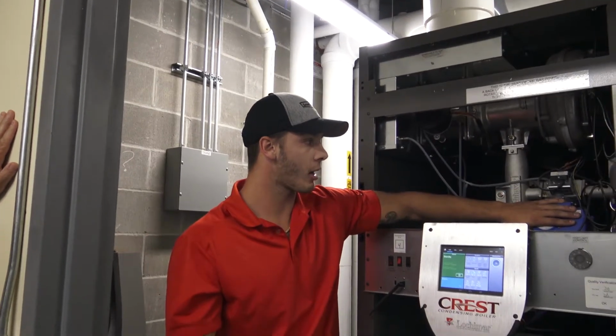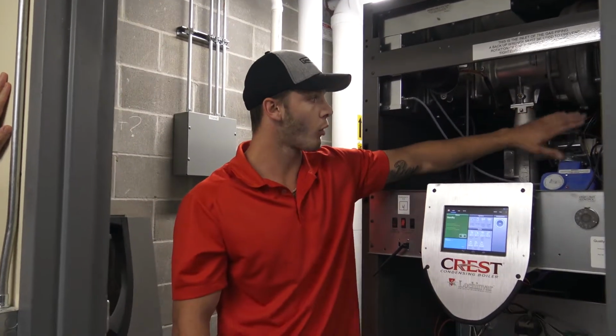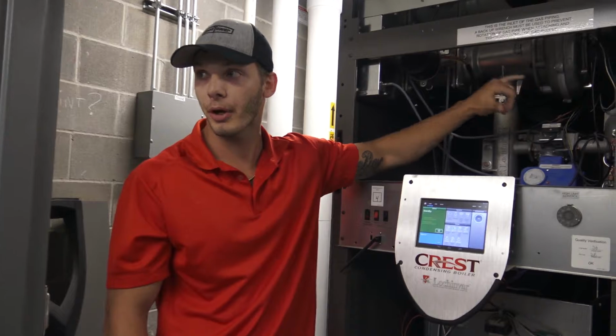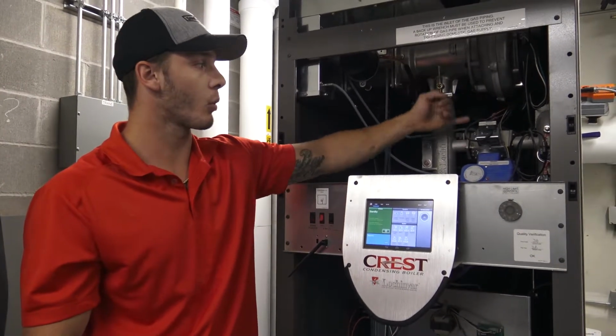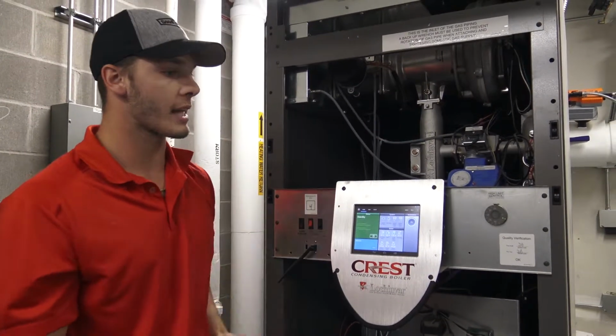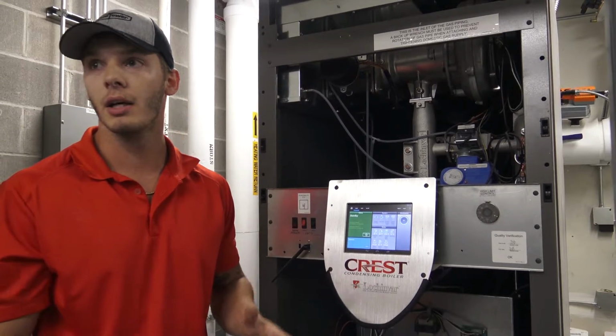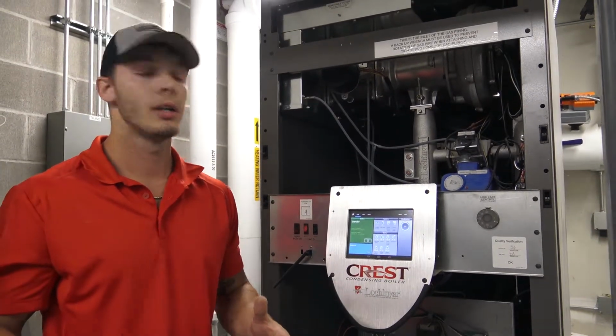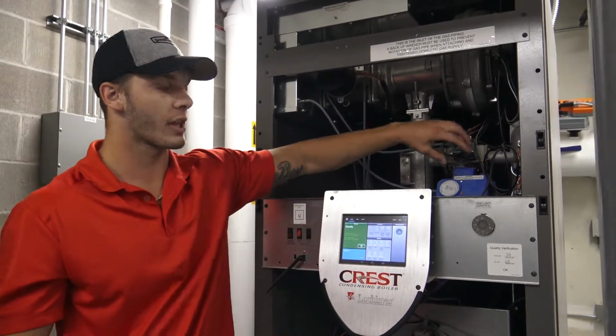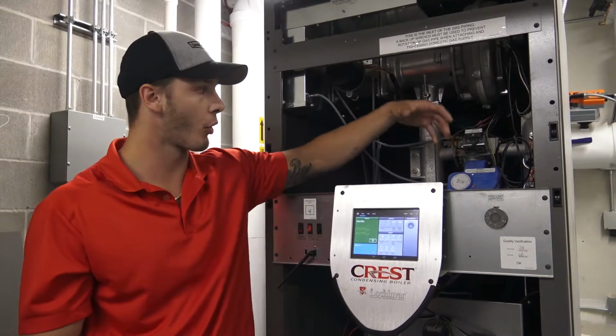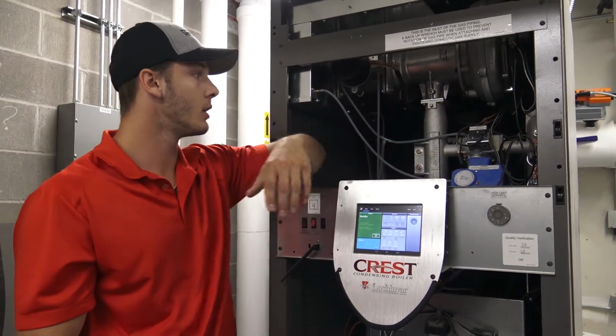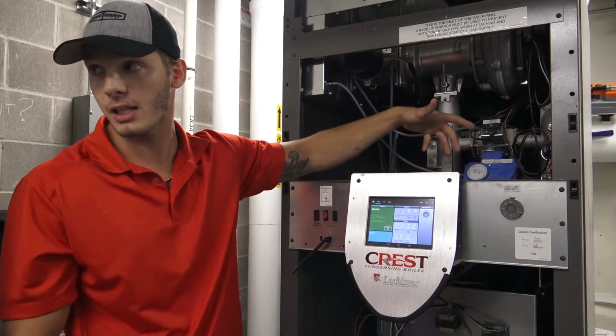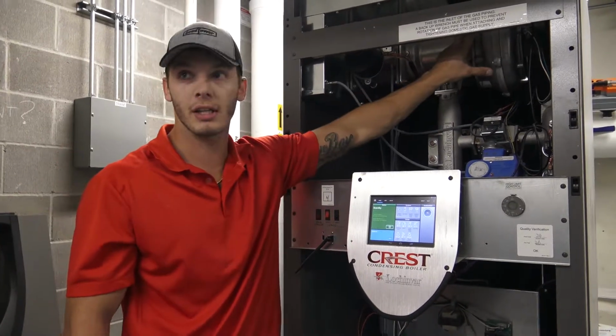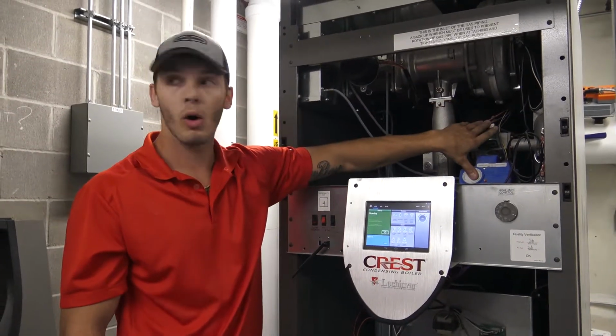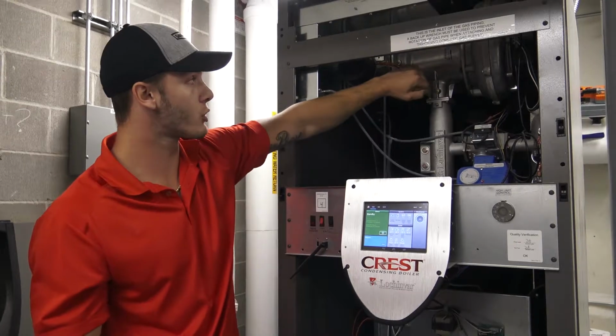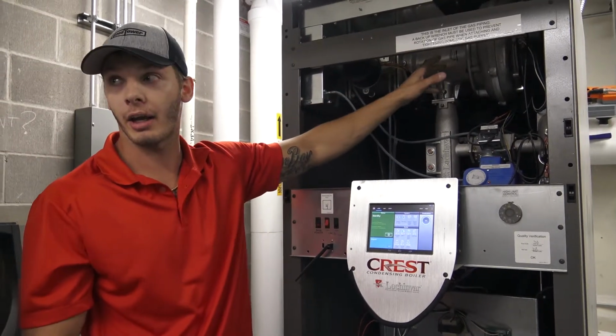This is your blower. It is going to be pulling outside air. High gas pressure valve, so high fire valve, low fire valve. They will not operate at the same time. It's going to be one or the other. So once it hits past 25%, it's going to go into high fire, and it's going to switch over to this Honeywell gas valve. Both modulating gas valves, negative pressure gas valve. So pretty much the blower is going to suck the gas out of the valves up into the venturi and pre-mix it.